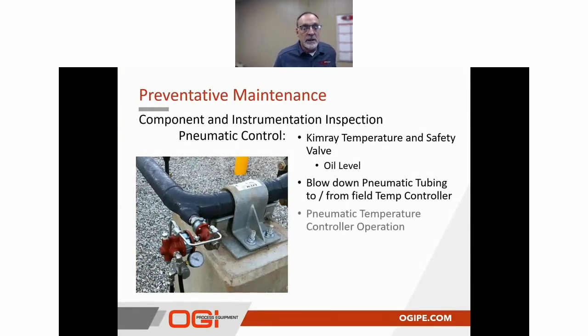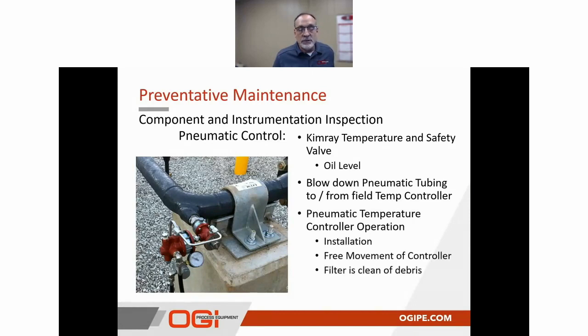We also want to inspect the pneumatic temperature controllers. We want to ensure that they're installed properly, so that they're not potentially collecting water onto the top where the control set point is adjusted. We want to make sure that control adjustment is free to move. If it's not free to move, that's an indication that the mechanism internally is somehow questionable, and it needs to be maintained and possibly replaced.